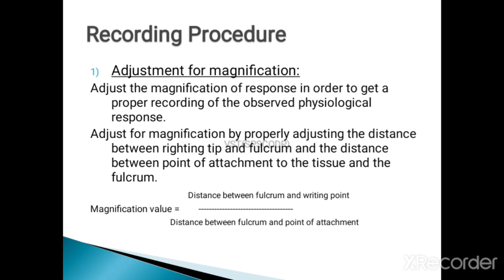Adjust for magnification by properly adjusting the distance between writing tip and fulcrum. The writing tip is attached to the recording drum and records contractions. The magnification formula is: magnification value equals distance between fulcrum and writing point divided by distance between fulcrum and point of attachment.